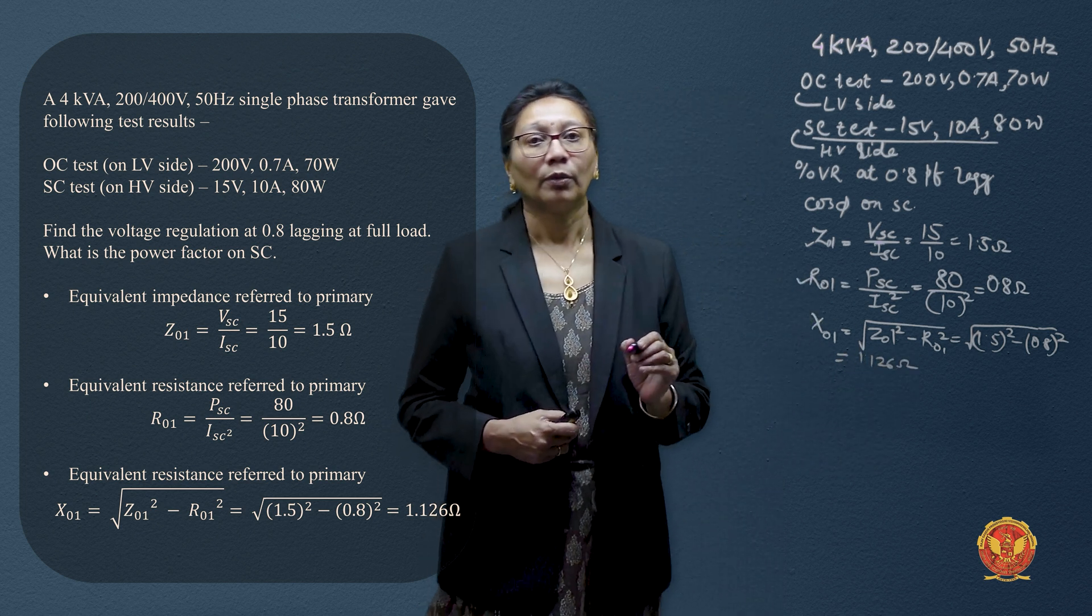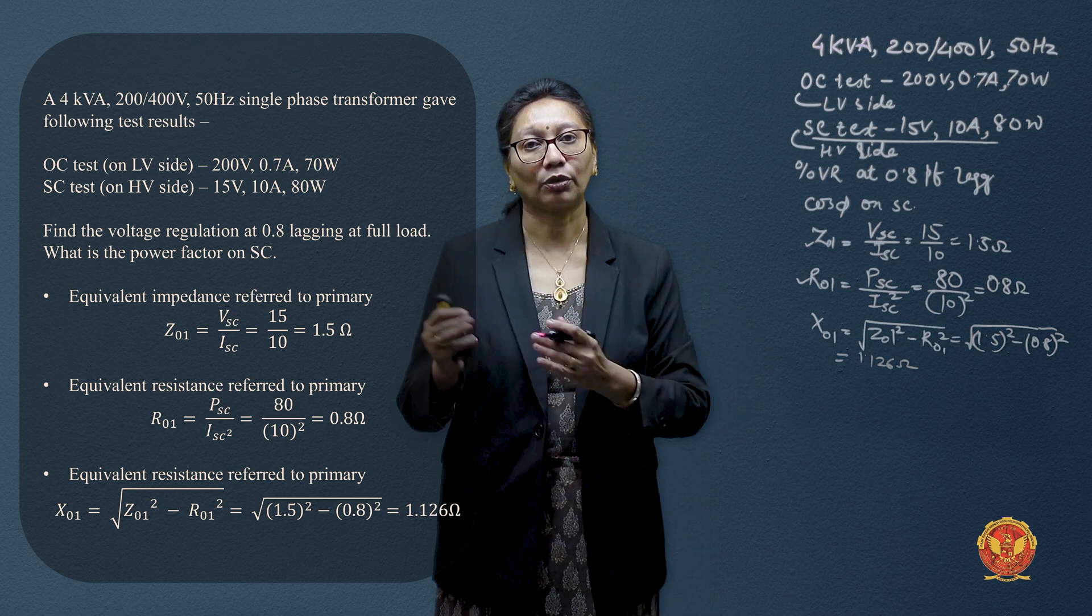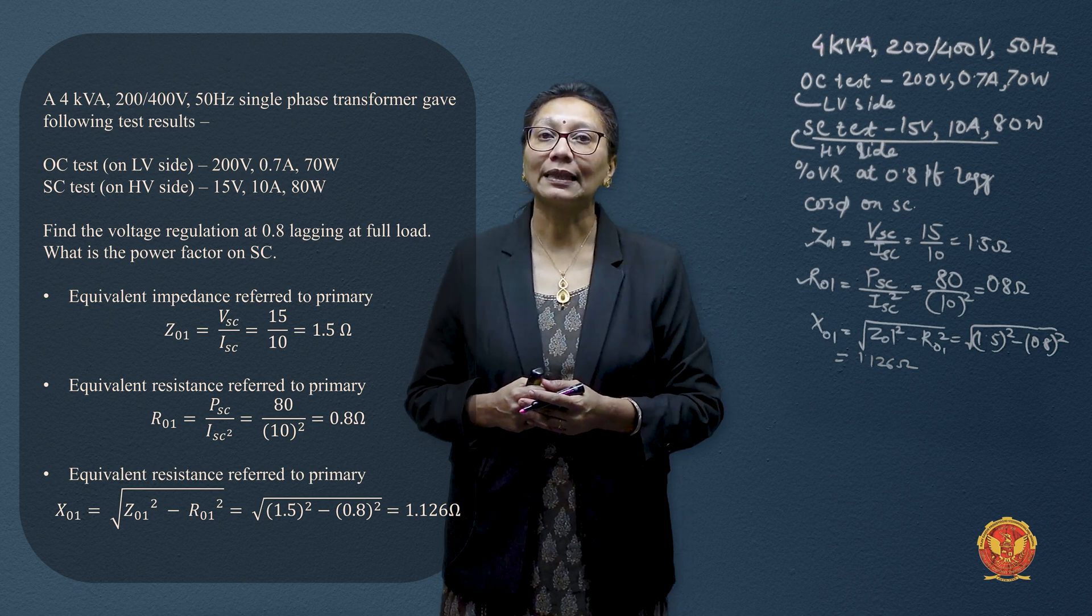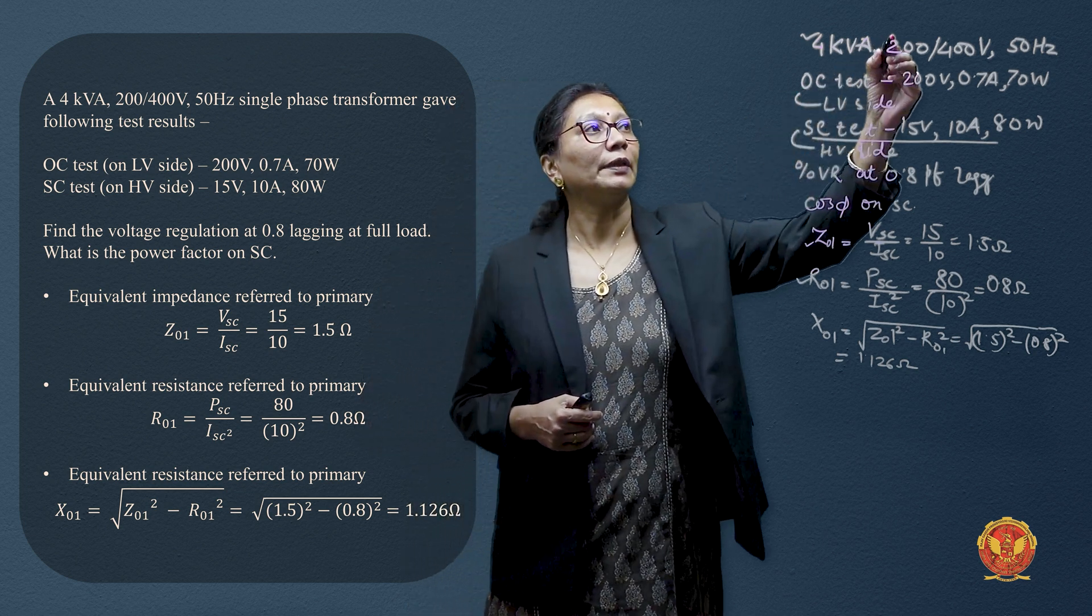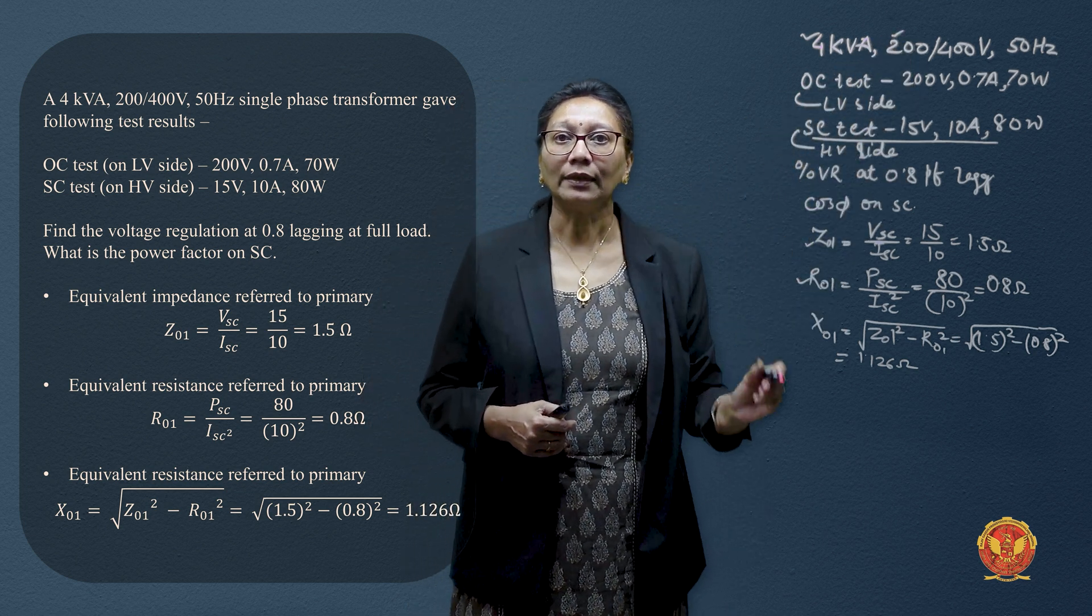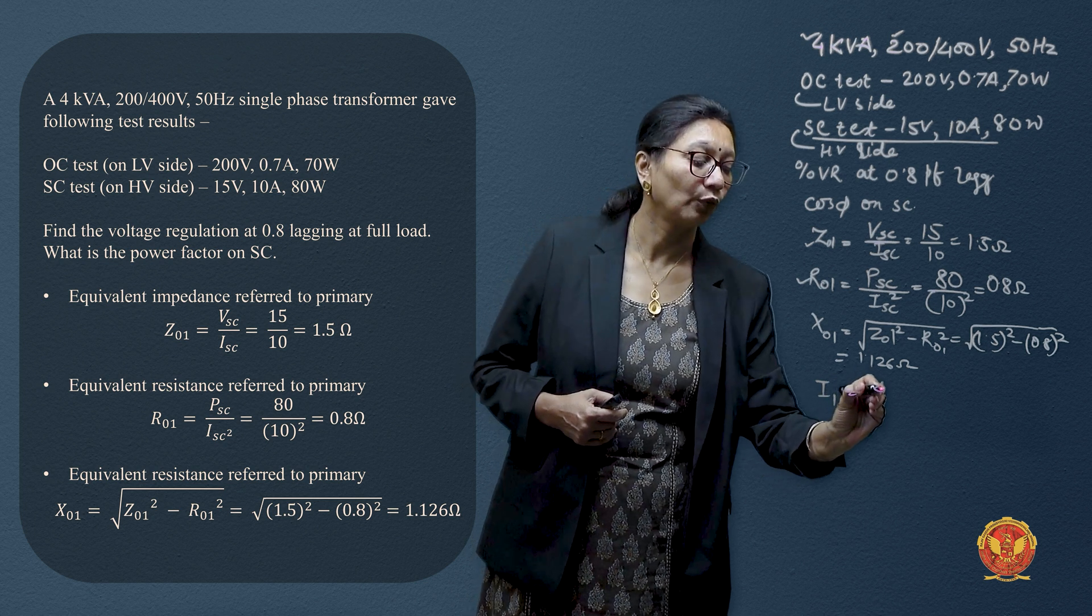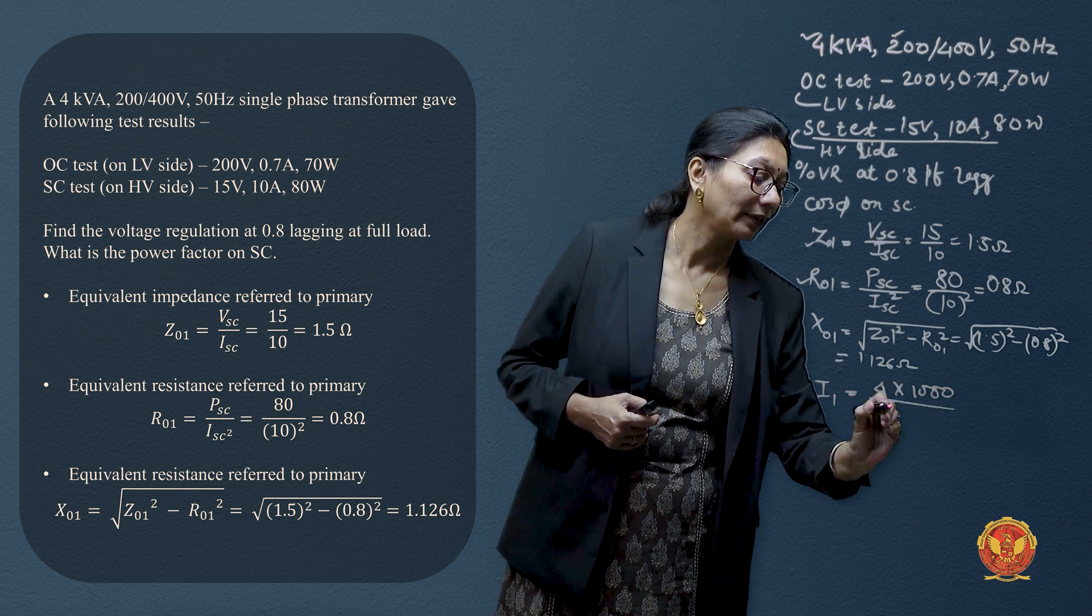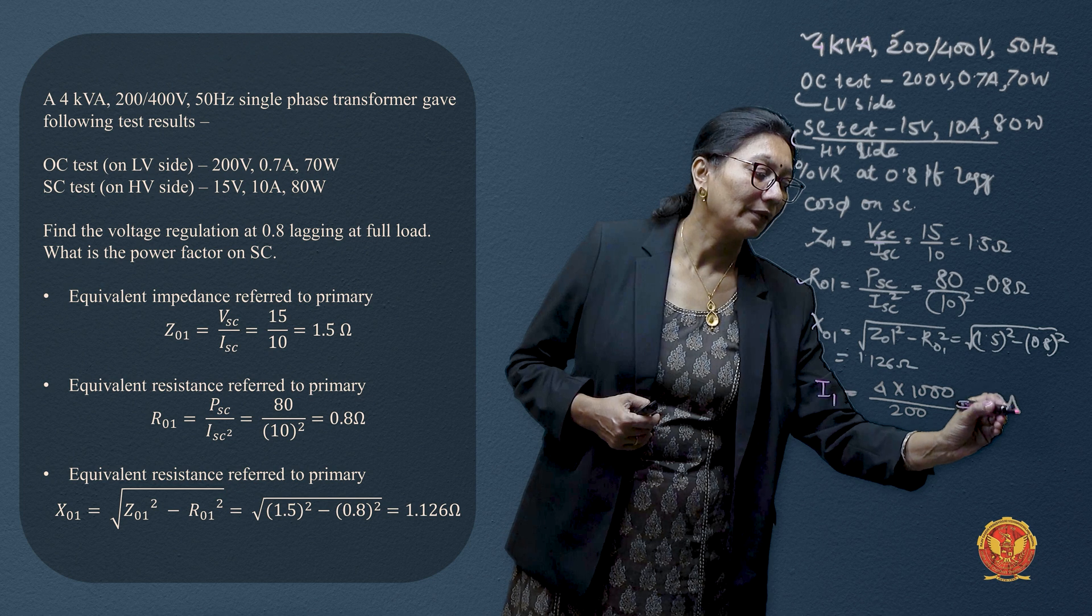Now we need to know primary current also when we talk of regulation of transformer. So primary current how to calculate? We have kVA rating and we have primary voltage. So primary current would be I_1 is equal to 4 into 1000 divided by 200. This gives us current is 20 amperes.